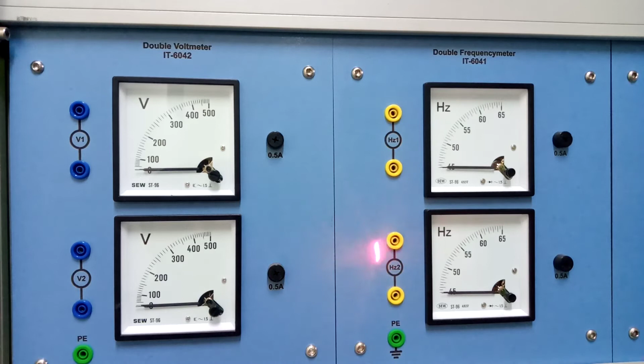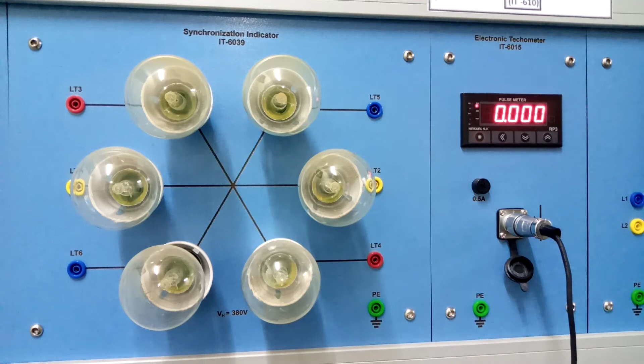This is our main trainer, the main module of our experiment, the synchronization indicator. We have three inputs on the left side and three inputs on the right side as well. The red phase of both the bus bar and the synchronous generator will be connected here, then the yellow phase and the blue phase. Normally there is one bulb, but here we have two bulbs connected, which gives us the synchronization indication. We also have a tachometer, which gives us the speed of our alternator.